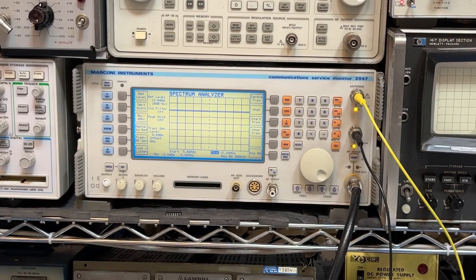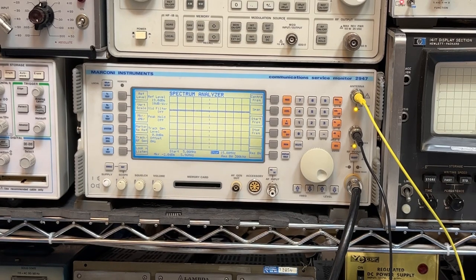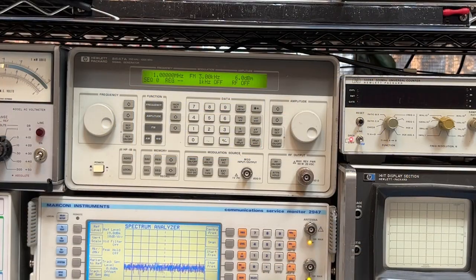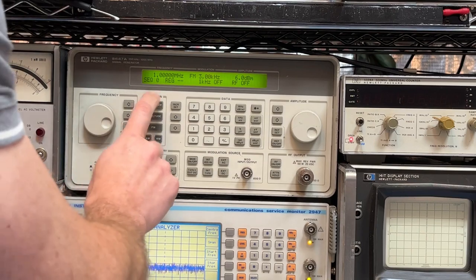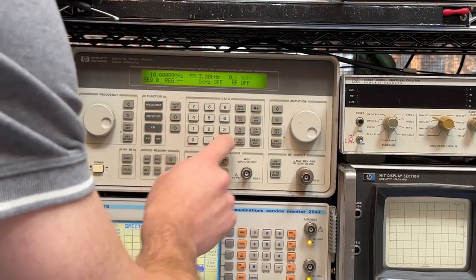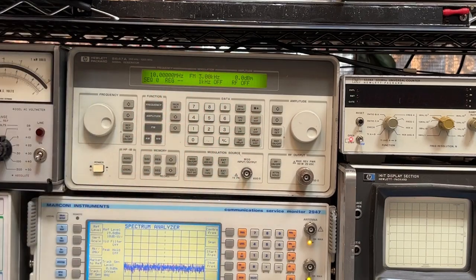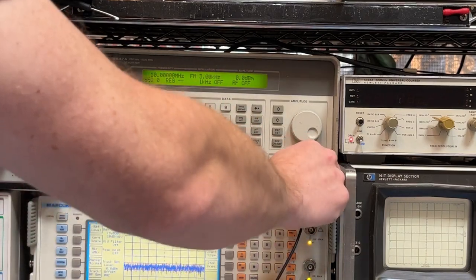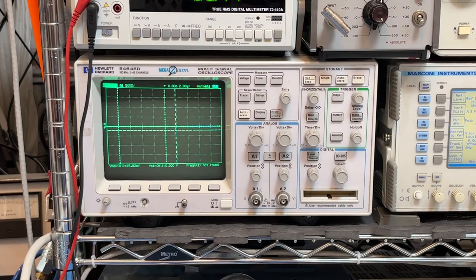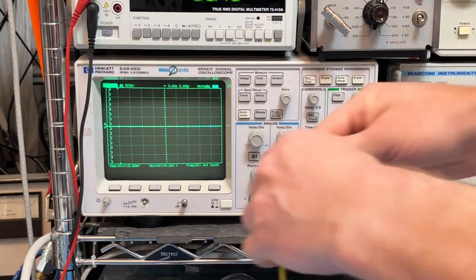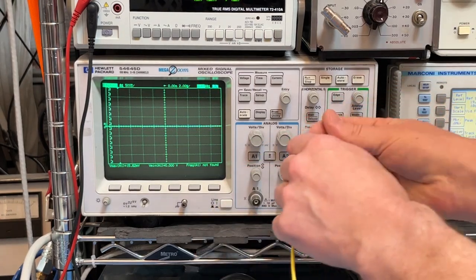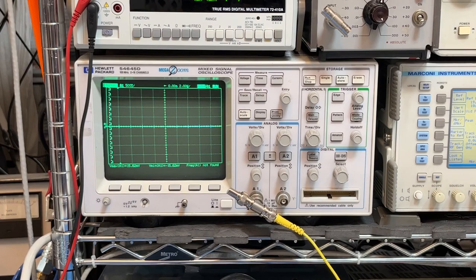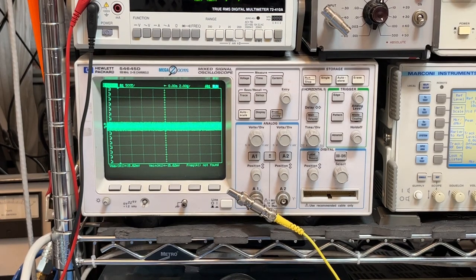Why don't we check out the waveform and the headroom. For this test, I'll use this HP 8647A as a generator. Frequency 10 MHz, amplitude 0 dBm. And we'll look at the amplitude range it supports in a minute. And what we'll do is we'll return the signal into the scope here. Let me grab a 50 ohm terminator. I'm going to turn on the RF.